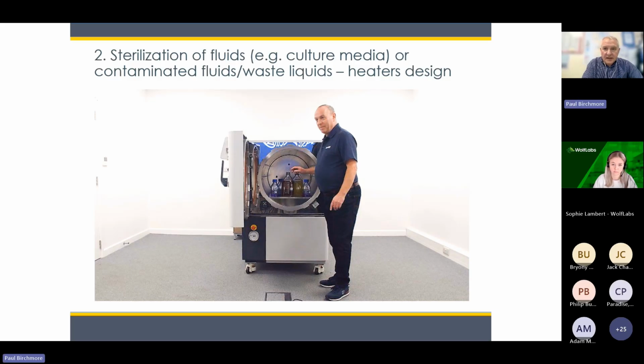So just to simplify that even further, what Neil was drawing attention to with his initial bottled media loads is that it's typically done in an autoclave with what we call heaters inside the chamber, which I could also simplify by saying it's a wet chamber. It's got water and a heating element inside the chamber. That means that the whole chamber will contain water. There will be water at the bottom of the chamber. I'm going to call that a wet chamber.